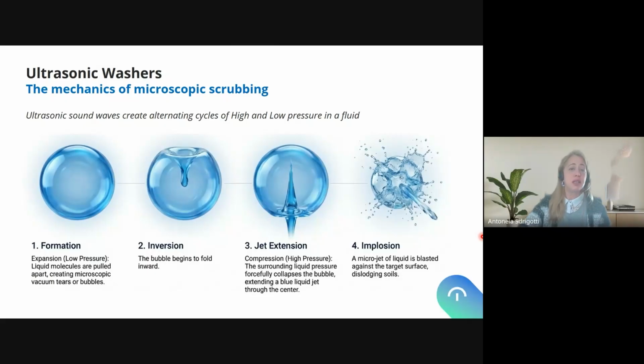So how is the mechanics of the microscopic scrubbing that we have inside an ultrasonic washer? Ultrasonic sound waves created by the transducers create alternating cycles of high and low pressure inside the fluid, inside the washing solution. So this is what happens. First, we have the formation. Cavitation is the creation of vacuum bubbles, not air bubbles, but vacuum bubbles, void bubbles. This happens because of this low and high pressure created inside the water that will create these cavitation bubbles that I will explain next.